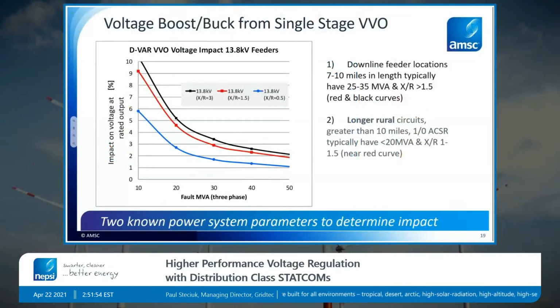So here's a graph that is a convenient tool to see how much impact a shunt, in this case a VVO STATCOM, can have when installed on a power system. You just need to know two parameters. Number one, the fault power, and that's along the x-axis, and then the X over R ratio. Both of those power system parameters are well known. The utility knows them. Most large facilities have that data readily available too. And with those two parameters, it can be determined how much voltage regulation ability a VVO STATCOM has.